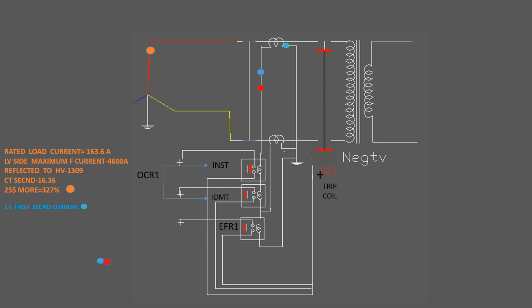Let's see how this earth fault relay will work. If any earth fault exists between the CT and the power transformer winding, leakage current will flow, and as it is close to the transformer primary, it is harmful. So when the current is more than the setting, that means the current setting is 10%, and the other settings I have already shown, when it reaches or exceeds that, the CB will trip. I have not shown the CB on the secondary side. Both CBs will trip through the inter-trip relay to make the transformer dead. Now see, the earth fault, earth leakage is continuing. How?